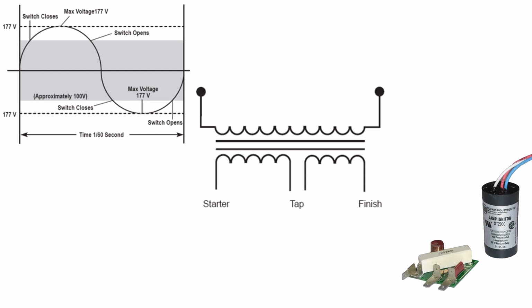First, it's important to know that HPS lights are part of the group called HID lamps, or high intensity discharge lamps. This includes mercury vapor and metal halide lamps too. But HPS fixtures have one special part that others don't: the starter. That's what makes HPS troubleshooting a little different.